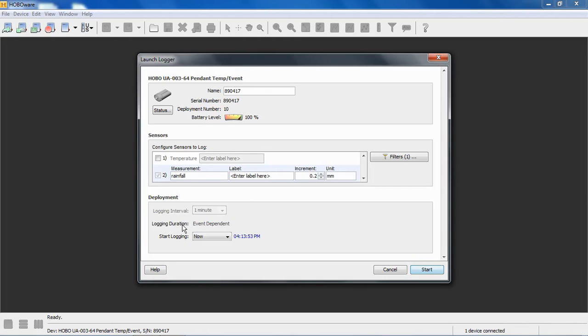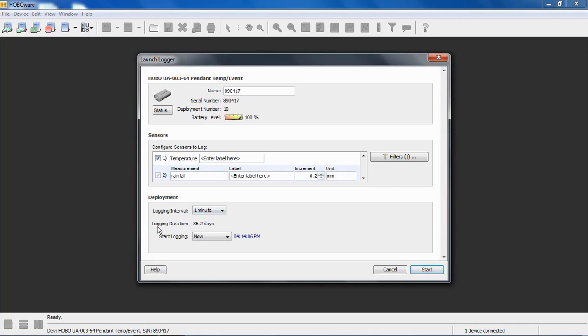And again, you see here, calculated logging duration is really event dependent. It depends on how many events you get. If we select temperature again, this is where we can put in the interval and at a one minute, what this is saying, a one minute interval, the logger will log for 36.2 days before the memory fills and the logger stops logging. This logger will stop logging when the memory fills up.